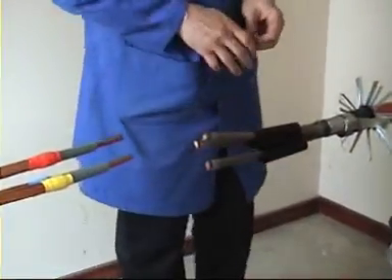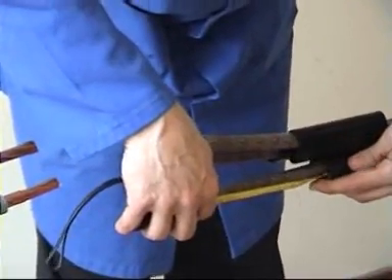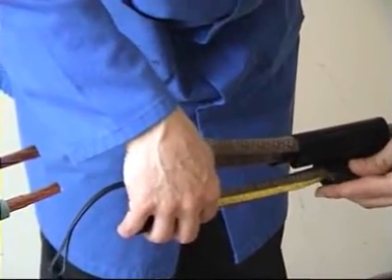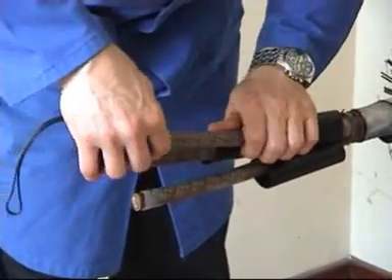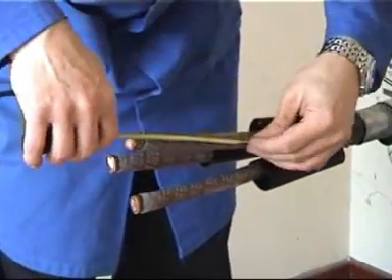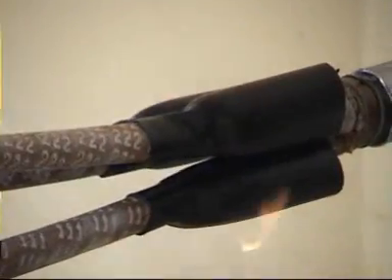Now we turn the paper belted cable into a screened cable by means of fitting conductive heat shrink sleeves. Position the conductive sleeves so that you achieve the dimension as specified in the instruction sheets from the end of the conductive sleeve to the end of the cores. Using a gas torch, shrink the sleeves into position.